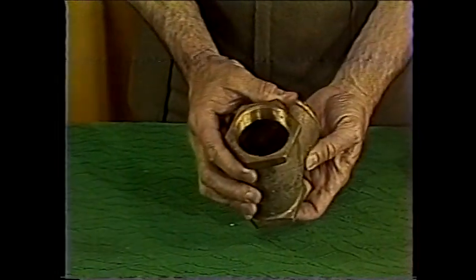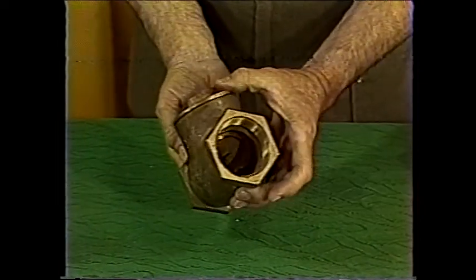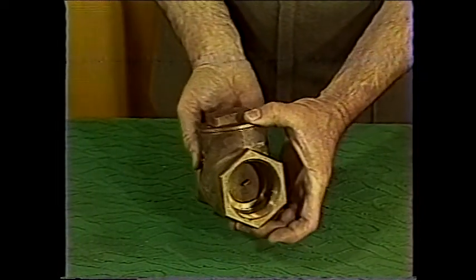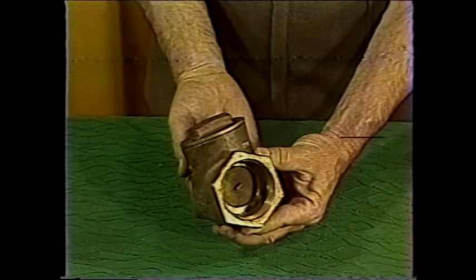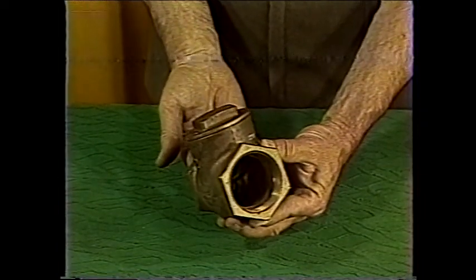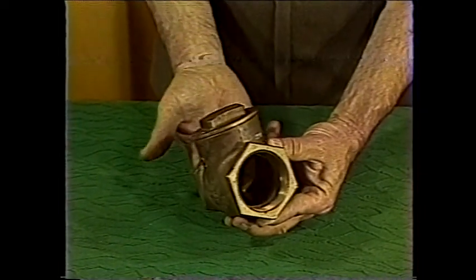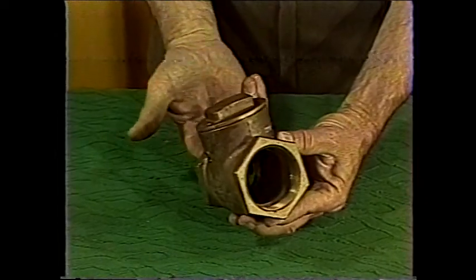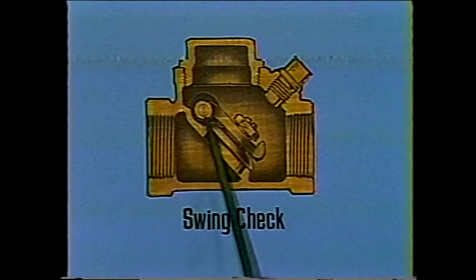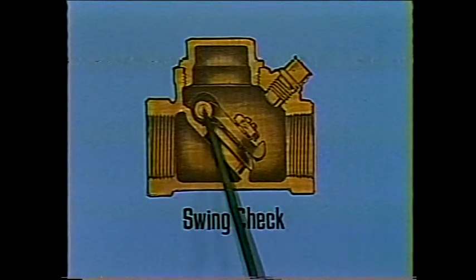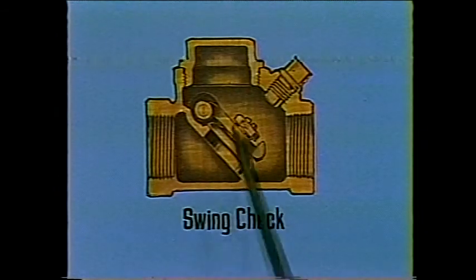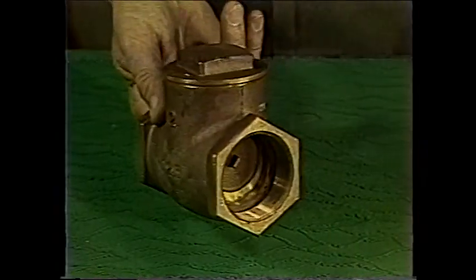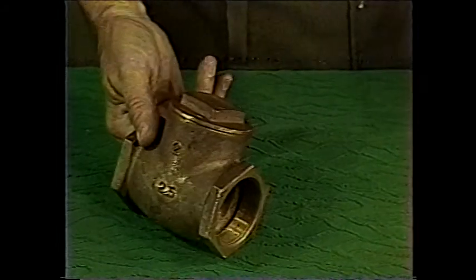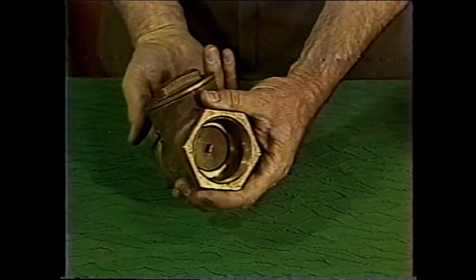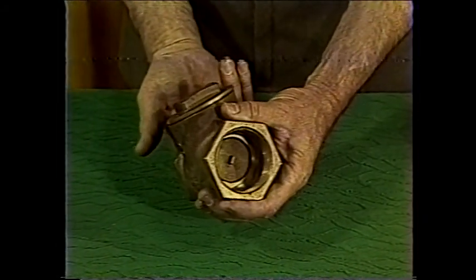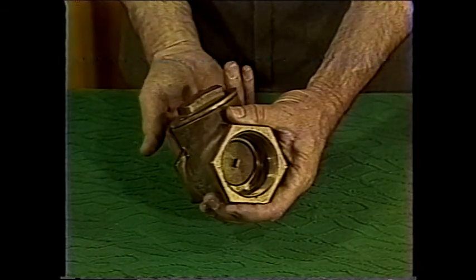Frequently, in a piping system, we desire to allow free flow in one direction, but to stop flow in the other. This is accomplished with what we call a check valve. The most common is the swing check, where we have a hinged flapper or disc which is moved up and out of the way by the pressure of the flow against it. When the flow is reversed, the flapper seats and is held in place by the back pressure on what is normally the outlet or downstream side.